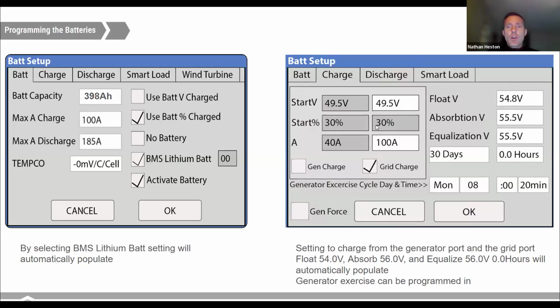For charging sources from AC, when you click on the charge tab on the top, you have the ability to independently set the rate of charging from the generator or from the grid ports. From the generator port, this is showing 40 amps. It's grayed out because this box is not checked. If you have voltage checked over here, then you would be setting the start value with a voltage. If you have percentage checked, then the percentage box would be what you are able to set.